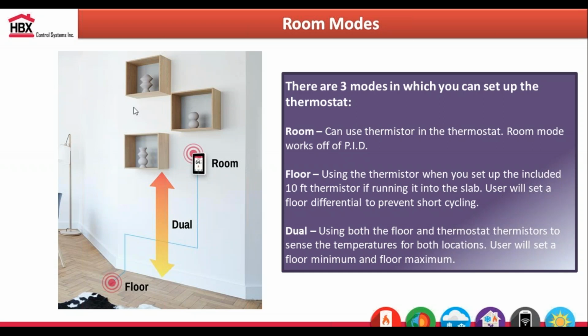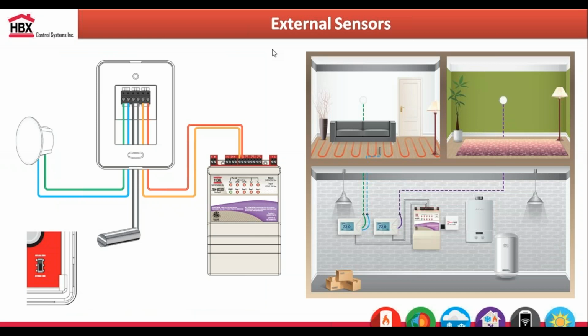That was because they put these control panels into the concrete, into the floor, so it was shielding the RF, and it was too far of a distance to get through. But it's rated for 2,000 feet for communication. Again, it's just open air.